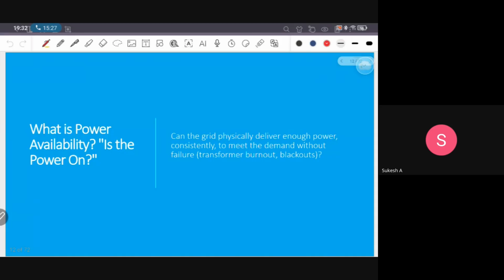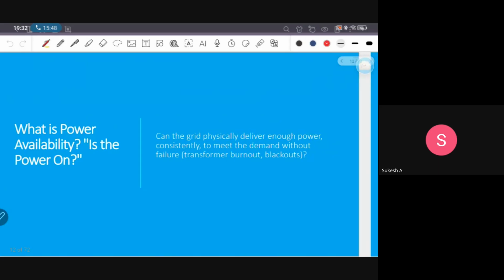This power generation for a very short duration needs optimization. We have to use other, really fast acting energy sources. Otherwise the transformer will burn out, or a blackout will happen. Transformer burnout is an irreversible process. We have to replace the transformer coils and transformers, whereas blackouts can be reversed with fast acting fuses or circuit breakers.